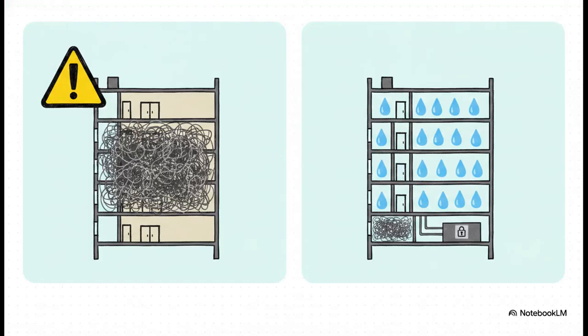The core difference here? It's honestly night and day. With a standard VRF setup, you are pumping large volumes of refrigerant all throughout the occupied spaces of a building. And that brings up a ton of regulatory and safety concerns, especially when you look at newer building codes. This hybrid approach, though, completely flips the script. It keeps all that complex, heavily regulated refrigerant contained far away from your living spaces and swaps it out for safe, simple water for the indoor delivery. It fundamentally alters the safety profile of the entire building.